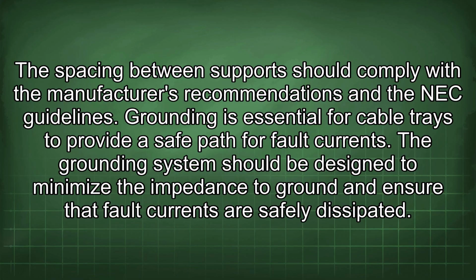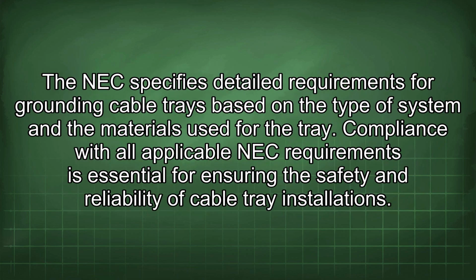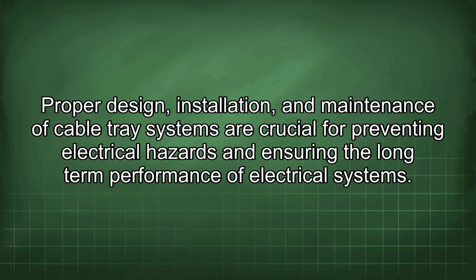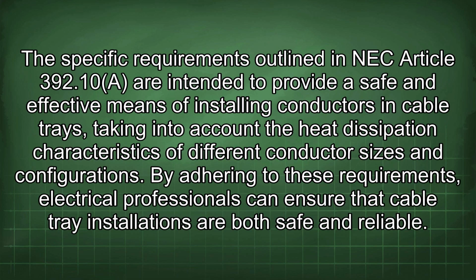Grounding is essential for cable trays to provide a safe path for fault currents. The grounding system should be designed to minimize the impedance to ground and ensure that fault currents are safely dissipated. The NEC specifies detailed requirements for grounding cable trays based on the type of system and the materials used for the tray. Compliance with all applicable NEC requirements is essential for ensuring the safety and reliability of cable tray installations. Proper design, installation, and maintenance of cable tray systems are crucial for preventing electrical hazards and ensuring the long-term performance of electrical systems. The specific requirements outlined in NEC Article 392.10 are intended to provide a safe and effective means of installing conductors in cable trays, taking into account the heat dissipation characteristics of different conductor sizes and configurations.